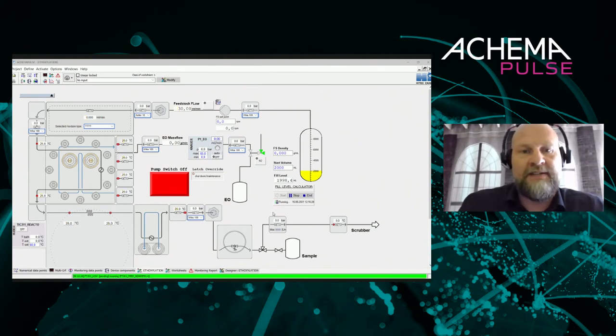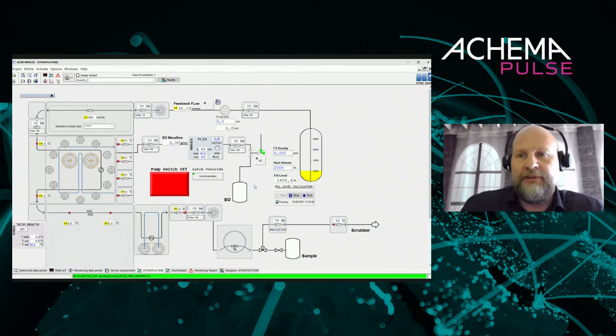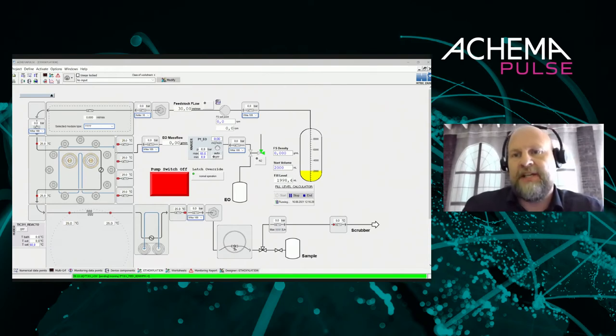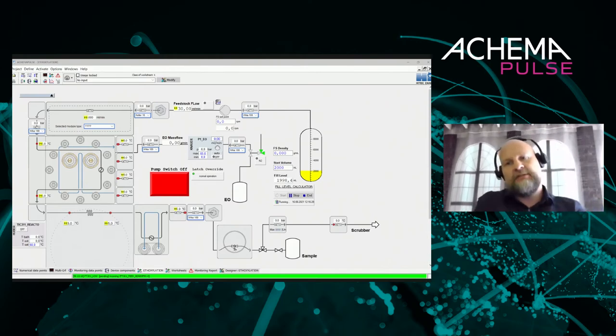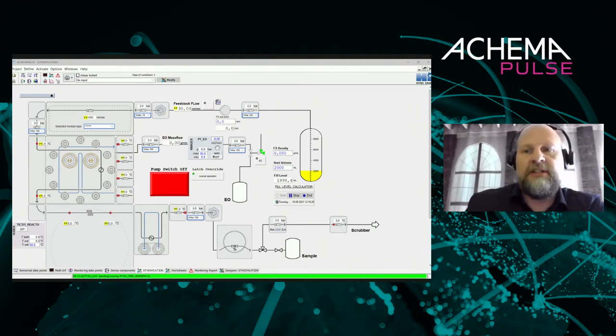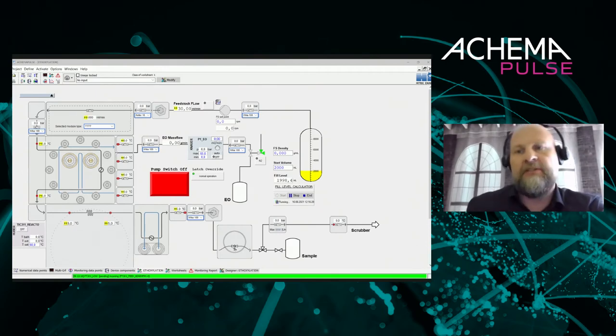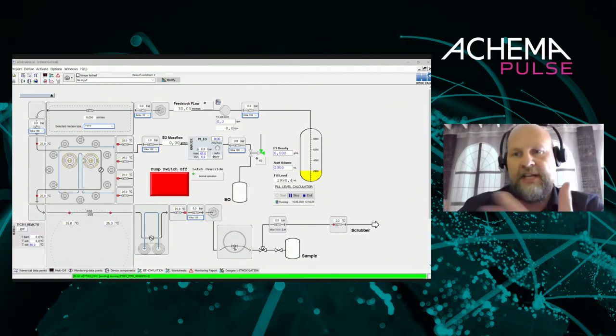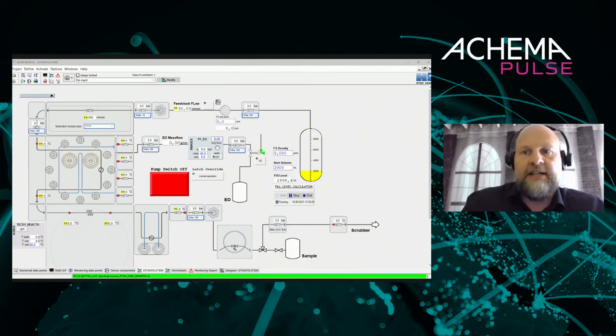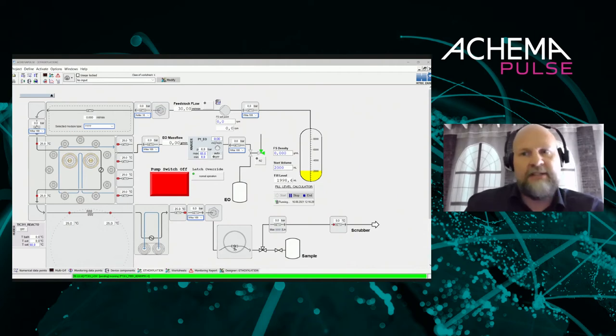Running in the background is a series of programs that give warnings when something goes wrong. For example, if the reactor temperature drops below a certain level, a warning is issued and the ethylene oxide is switched off, because insufficient heat means the reaction cannot carry on and unreacted ethylene oxide would pass through. Similarly, if temperature gets too high, or if the feedstock flow is low, warnings are triggered. These small programs can all be tested individually.